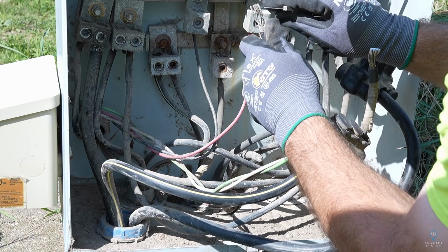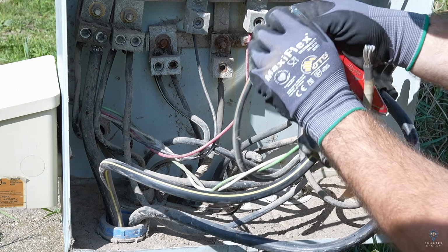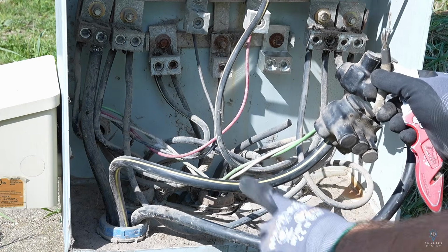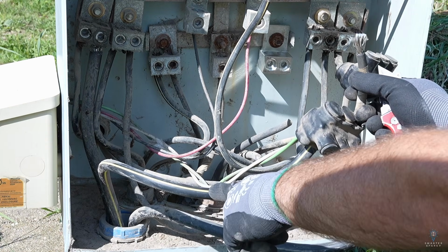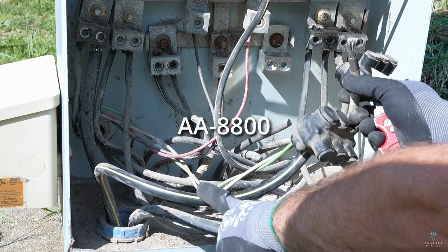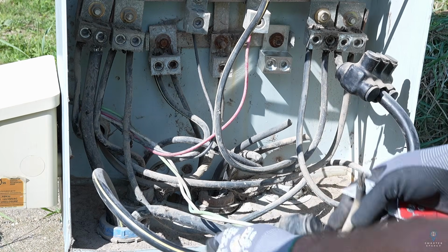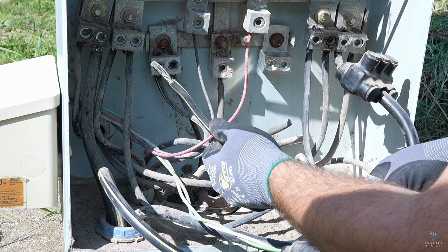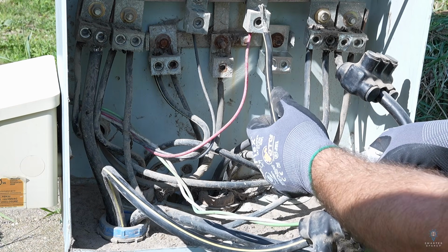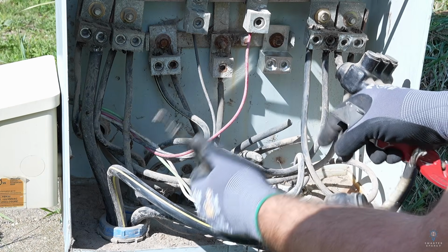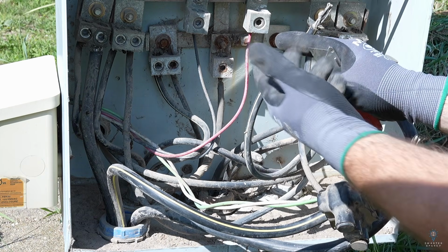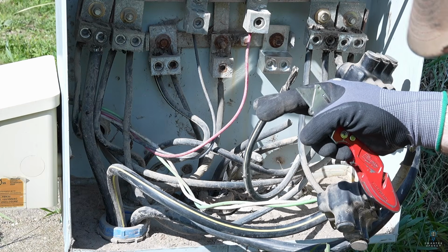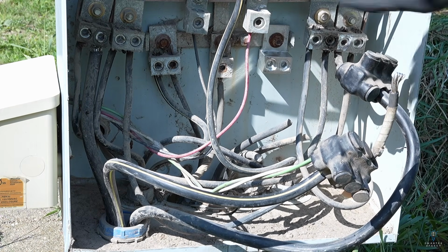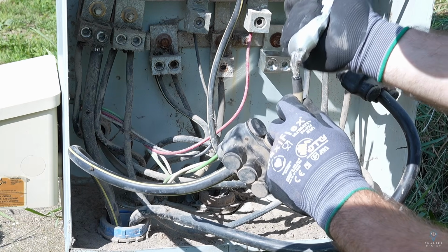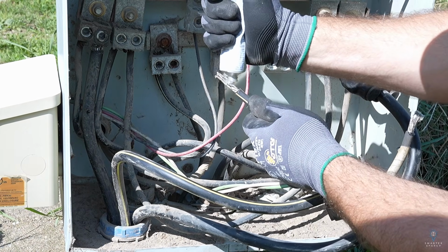I'm scraping a little bit of the old antioxidant off right now. Now, this wire right here for sure is that newer AA-8000 stuff. This, you don't have to put that antioxidant on. I am not sure how old some of these other conductors are. I'm gonna err on the side of this one. I'm pretty sure is a more modern one as well. So technically you don't have to put that grease on these conductors. These are aluminum conductors here. I am going to anyway, because, well, we obviously have a corrosion problem in here. Just gonna smoo a little bit of that on there. Smoo a little bit on here too.